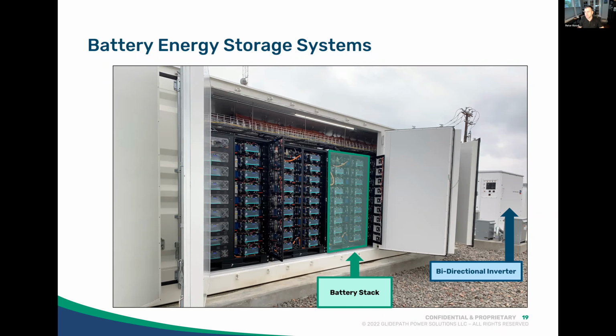I think on this project we can shut down at the rack level, so it's automated. If something deviates, it flags an alert for our techs. It shuts itself down, and then either someone goes out proactively or it's added to a list for the next maintenance cycle. These projects, like anything else—this is a multi-million-dollar piece of equipment—have a preventive maintenance cycle covering the things you mentioned and more. There is a lot of filtering, and I think most of it happens at the HVAC intakes. You can see the seals here. Once this thing is shut up, it doesn't get opened very often—maybe a couple times a year besides for photos like this. So it's less about managing stuff inside and more about keeping things out.